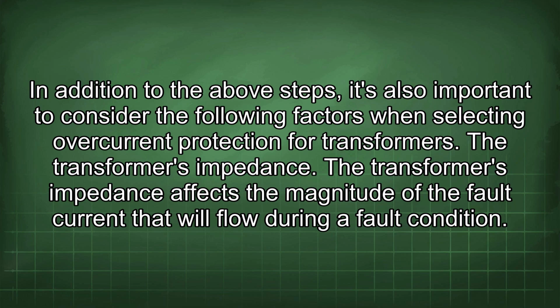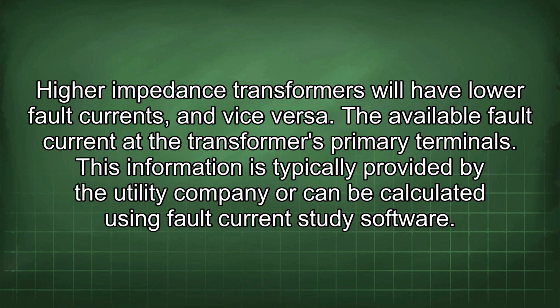In addition to the above steps, it's also important to consider the following factors when selecting overcurrent protection for transformers. The transformer's impedance. The transformer's impedance affects the magnitude of the fault current that will flow during a fault condition. Higher impedance transformers will have lower fault currents, and vice versa. The available fault current at the transformer's primary terminals. This information is typically provided by the utility company or can be calculated using fault current study software.